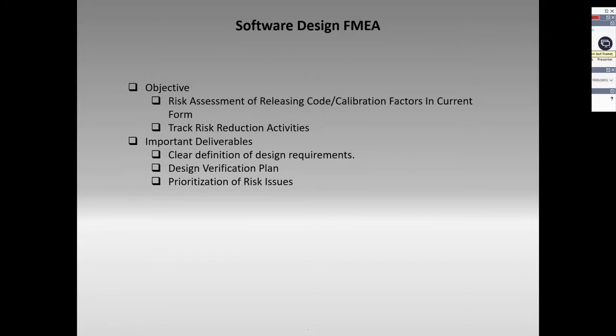Important deliverables are: we have to have a clear definition of what the design requirements are, and we have to have a design verification plan. Going back to what I talked about with risk - probability of exposure to objectionable incidents - this design verification plan is used to determine that occurrence.